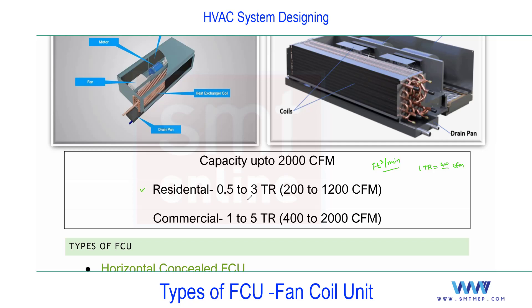Residential FCUs are available from 0.5 to 3 TR, which is 200 to 1200 CFM. Commercial FCUs go from 1 to 5 TR, up to 2000 CFM. The indoor air side unit is generally rated in CFM, while outdoor units such as condensing units or chillers are rated in tons, kilowatts, or HP.